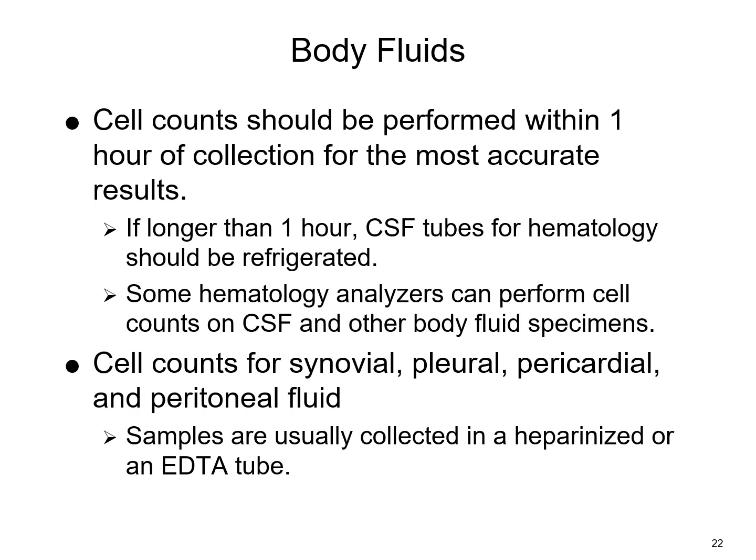Some hematology analyzers can do cell counts on spinal fluid and other body fluids. Some may not have the capabilities of doing those body counts, or may only have the capability to do it on certain fluids. So there are going to be situations where you probably will still have to resort to doing a hemocytometer count.